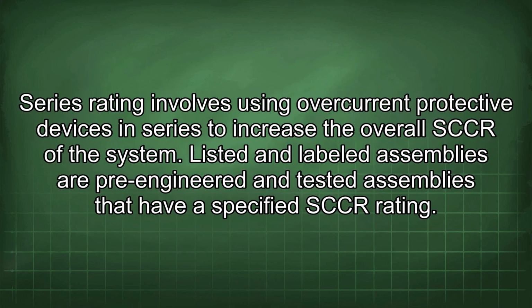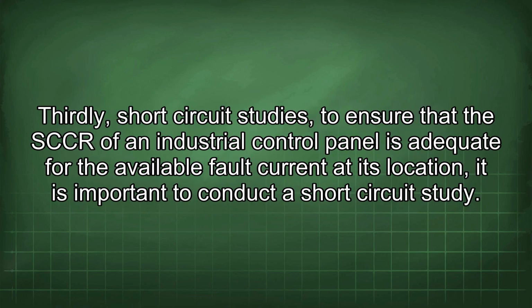Series rating involves using overcurrent protective devices in series to increase the overall SCCR of the system. Listed and labeled assemblies are pre-engineered and tested assemblies that have a specified SCCR rating. Thirdly, short-circuit studies. To ensure that the SCCR of an industrial control panel is adequate for the available fault current at its location, it is important to conduct a short-circuit study.